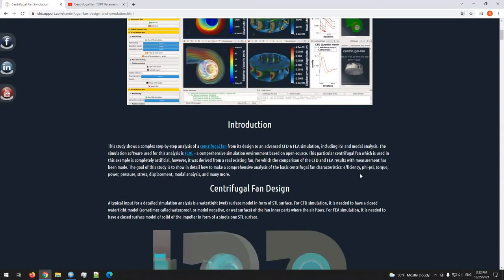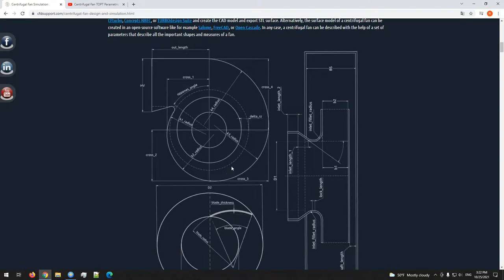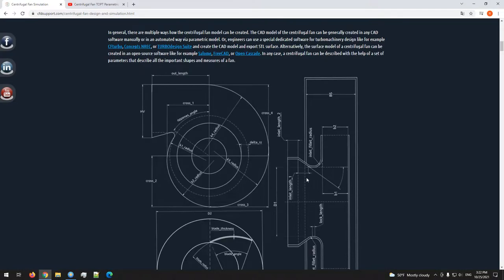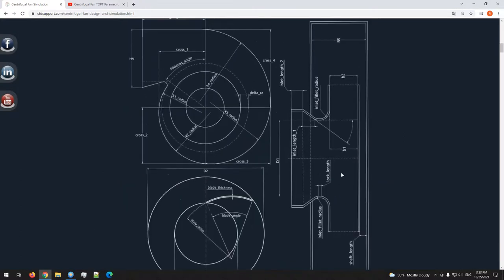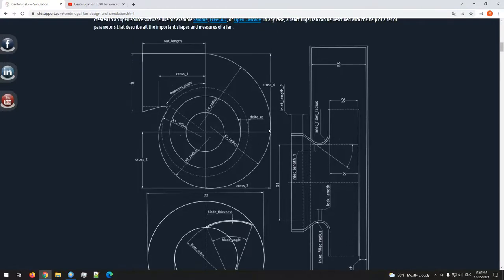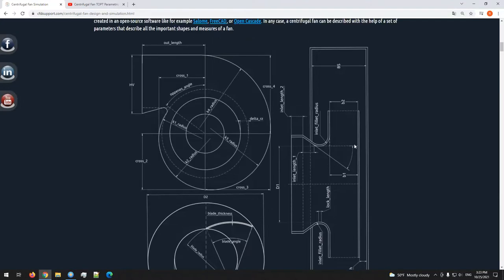So what we are going to do: we took this centrifugal fan design, for which we have developed a simple geometrical parametrical model in Salome via Python scripting. The model itself includes, I think, more or less 30 parameters to be set. For the optimization case, we pick, I think, 5 parameters, which are connected to the shape of the impeller itself.